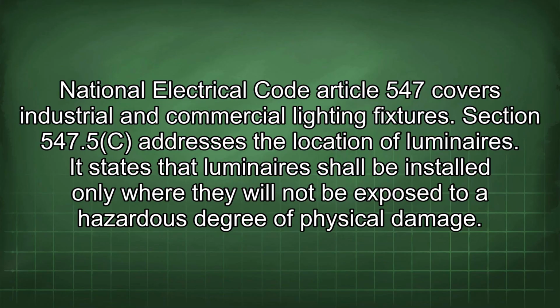National Electrical Code Article 547 covers industrial and commercial lighting fixtures. Section 547.5c addresses the location of luminaires. It states that luminaires shall be installed only where they will not be exposed to a hazardous degree of physical damage.